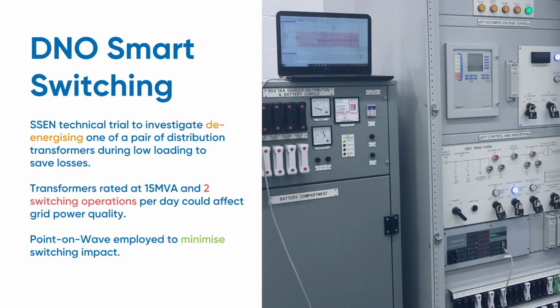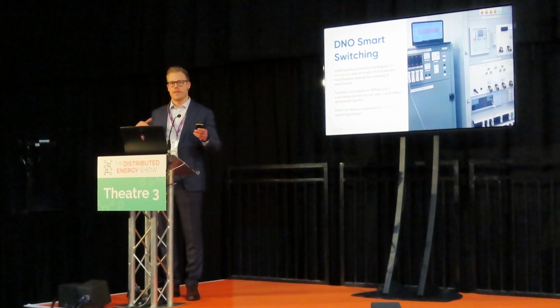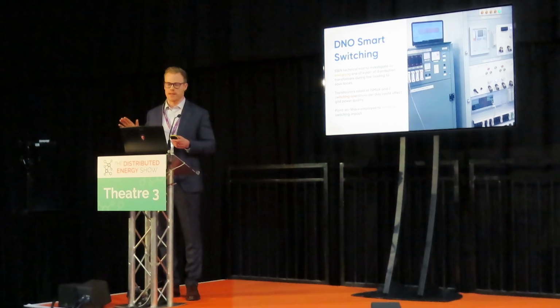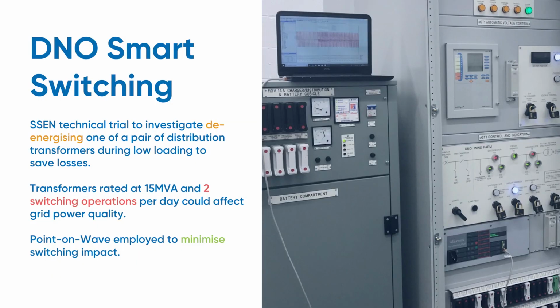So we looked at an initiative with SSEN. We would apply point-on-wave switching to a pair of distribution transformers. At a time of low load, one of those transformers would be switched out. Then when the load's coming back up, we'd switch that back in with point-on-wave, causing no impact to the network. And then that transformer will be there, but we've saved all the no-load losses in the meantime.